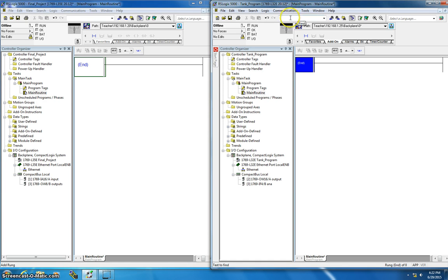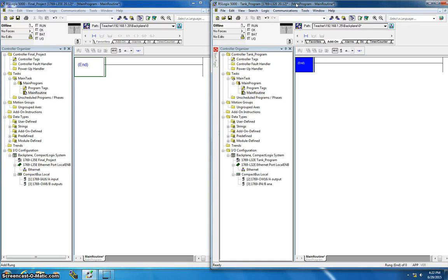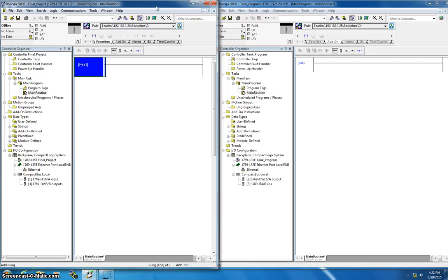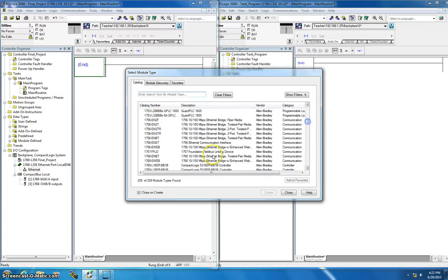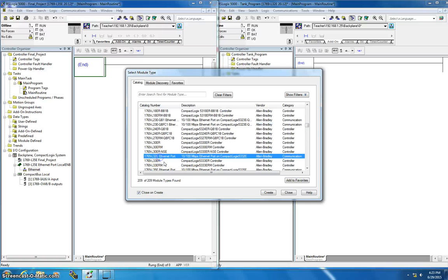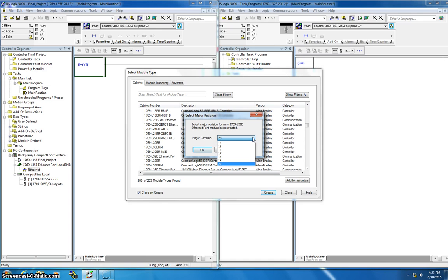The first thing we have to do is set up our Ethernet connection between the two projects. The L35E is the sender and the L32E is the receiver. We come down to IO configuration, go to Ethernet, and select new module. We scroll down to find the L32E with the Ethernet port and hit Create. Both are set to revision 20, so we hit OK — make sure you select the correct revision if yours differs.